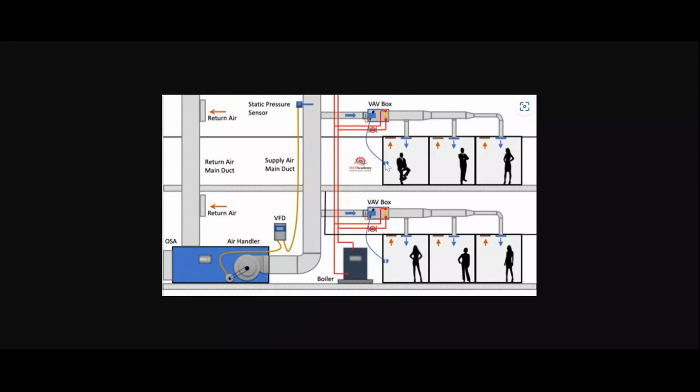This is using the chiller unit, sir. This is the AHU. Air is coming from the air handling unit at 18 degrees centigrade. Grill temperature is 18 degrees centigrade. If I supply 18 and supply 600 CFM to the room, the room will be at 24. That is our calculation. But now I don't want 24, I want 28.